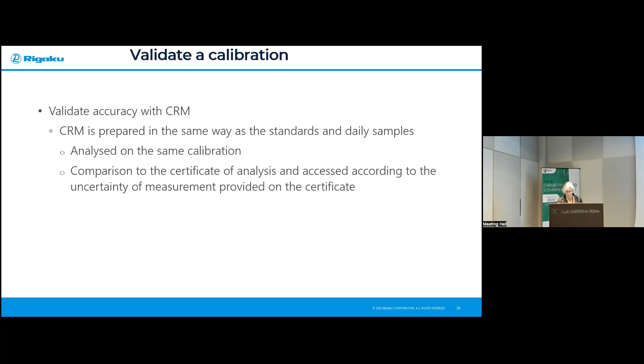What about validation? This is a process of basically proving that your analytical method is fit for purpose. So how do we do this? We do this by creating certified standards that are independent of your calibration method, and then comparing this to the certificate of analysis to assess if the uncertainty of method is provided is correct from the certificate. Yes? So here you can see the example. If you have time, you can go through it because I don't have enough time to explain it. So I will just skip it.